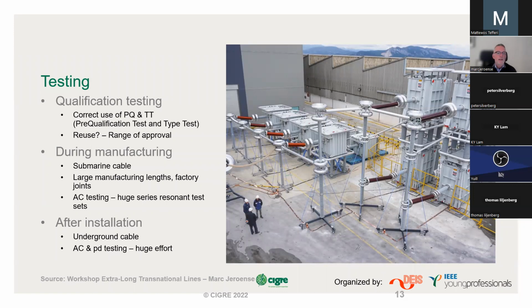One can do so, and it is being done and discussed on shorter sections of length. The trend there is also concerning if you look to the future—larger lengths and higher voltages will become a challenge too. At the moment, I think it's necessary, because we've never had this top level of voltage in cable systems, 525 kV. But maybe in future, once we get used to it and see the performance during after-installation testing, we might say that AC and PD testing is no longer necessary.